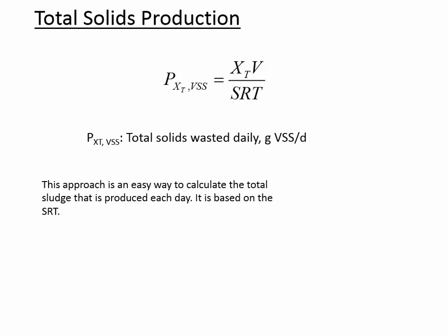They're dissolved. And the same thing is true of BOD. If it's dissolved, no amount of settling is going to take a dissolved constituent and take it to the bottom of the clarifier. So what we do instead is we turn that dissolved mass into a settleable mass, into new cells. And this is the most basic way for us to estimate the rate that solids are being produced inside of the aeration basin, inside of the secondary treatment.